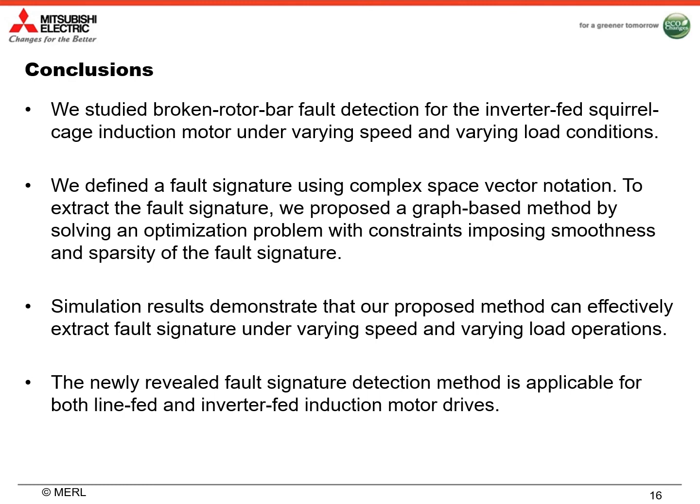Here are our conclusions. We studied broken rotor bar fault detection for the inverter-fed squirrel cage induction motor under varying speed and varying load conditions. We defined a fault signature using complex space vector notation. To extract the fault signature, we proposed a graph-based method by solving an optimization problem with constraints imposing smoothness and sparsity of the fault signature. Simulation results demonstrate that our proposed method can effectively extract fault signature under varying speed and varying load operations. The newly revealed fault signature detection method is applicable for both line-fed and inverter-fed induction motor drives.